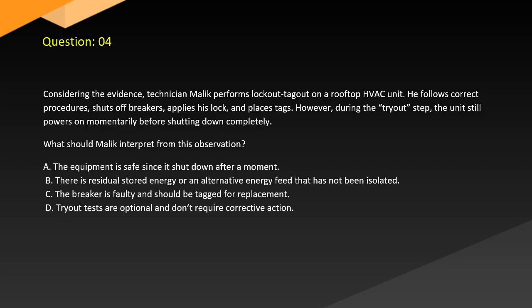Question 4. Considering the evidence, technician Malik performs lockout tagout on a rooftop HVAC unit. He follows correct procedures, shuts off breakers, applies his lock and places tags. However, during the tryout step, the unit still powers on momentarily before shutting down completely. What should Malik interpret from this observation? A. The equipment is safe since it shut down after a moment. B. There is residual stored energy or an alternative energy feed that has not been isolated. C. The breaker is faulty and should be tagged for replacement. D. Tryout tests are optional and don't require corrective action.